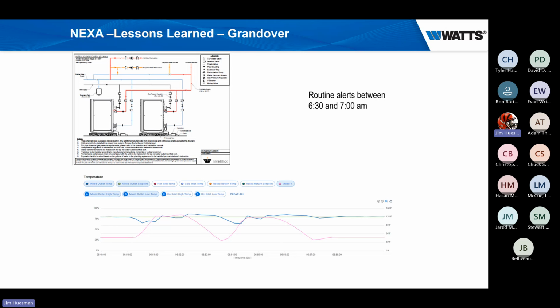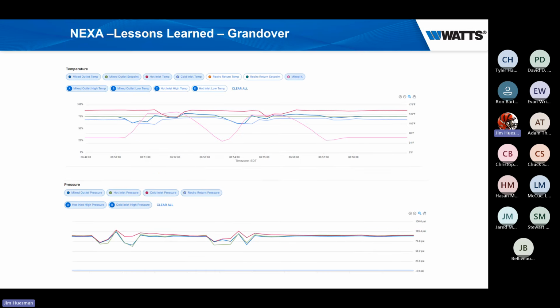So we jumped in, well it's not the mixing valve. We were able to troubleshoot it quickly to find out, hey, we're turning on a lot of equipment, we're having a major drop and losing a lot of water in the heaters. We were able to adjust that and get them right back online - and again, we were able to do that by just seeing those graphs.